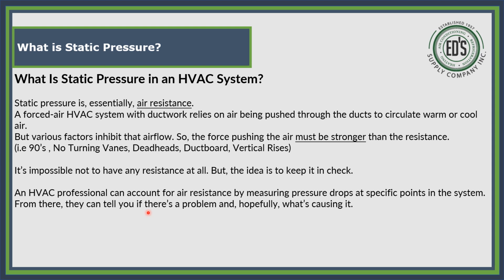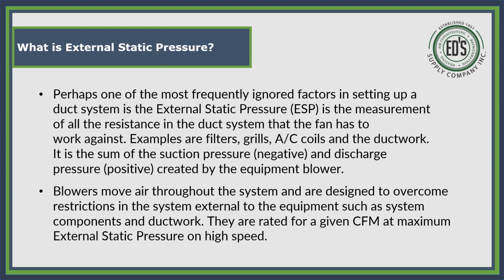So the force pushing the air, which is your blower motor, must be stronger than the resistance in the ductwork that's caused by the 90s and the turning vanes or deadheads or duct board, etc. It's impossible not to have any resistance at all, but the ideal is to keep it in check, much like your blood pressure is. An HVAC professional can account for air resistance by measuring pressure drops at specific points in the system. From there, they can tell you if there's a problem and hopefully what's causing the problem.